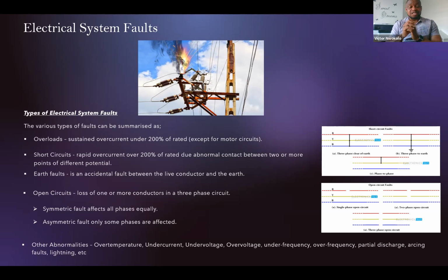We have, for the sake of summary, the electrical faults are within overcurrent and voltage variation. Everything else, should I say, is a variant of these two. It's either you get overcurrent, undercurrent, over voltage, or under voltage. Every other fault in the electrical system is a variant or is derived from this. So we look at the most common types of fault we've got.